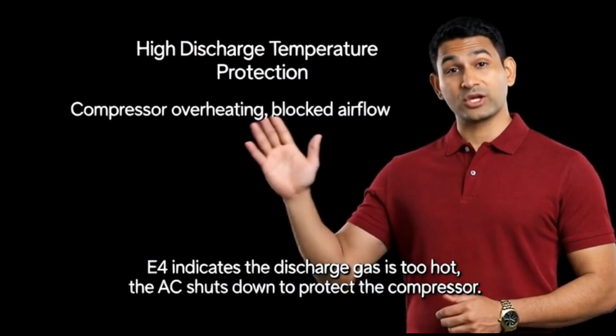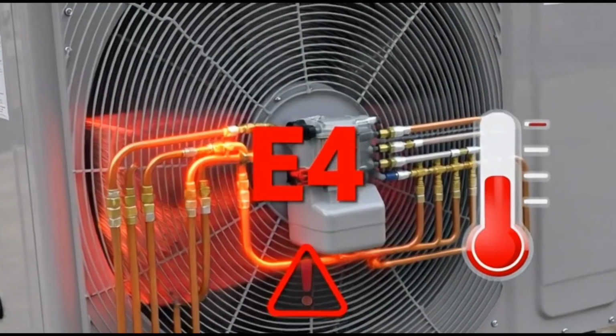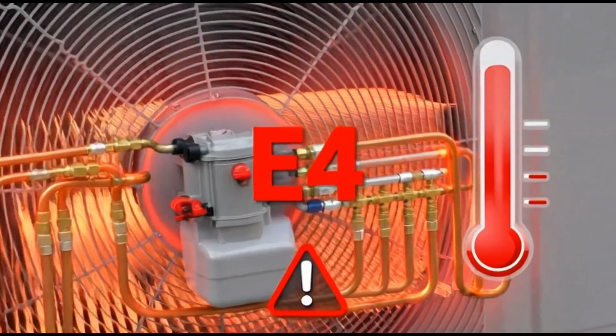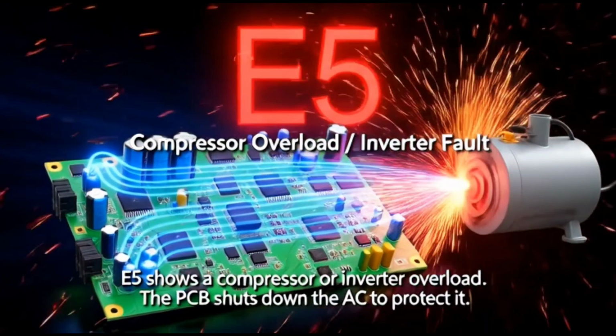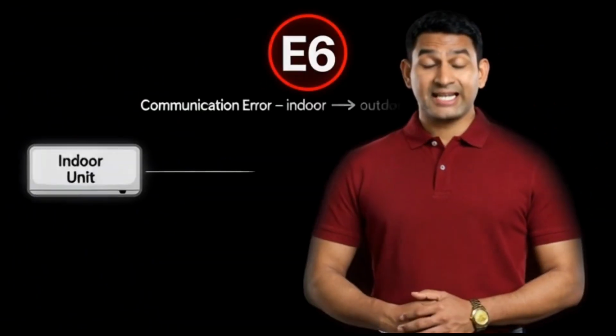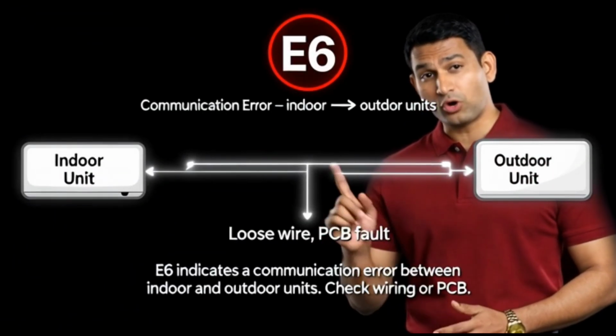E4 indicates the discharge gas is too hot. The AC shuts down to protect the compressor. E5 shows a compressor or inverter overload. The PCB shuts down the AC to protect it. E6 indicates a communication error between indoor and outdoor units.